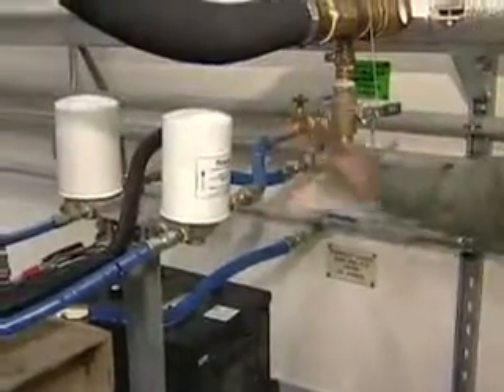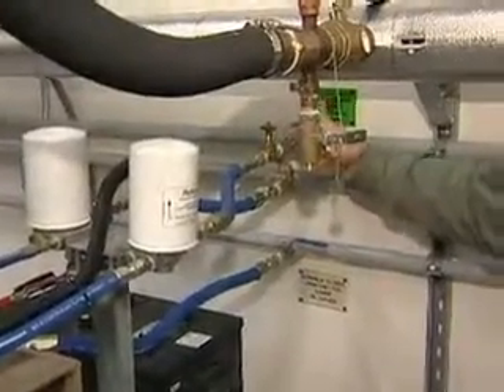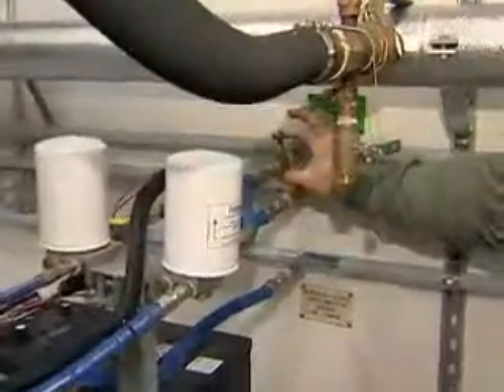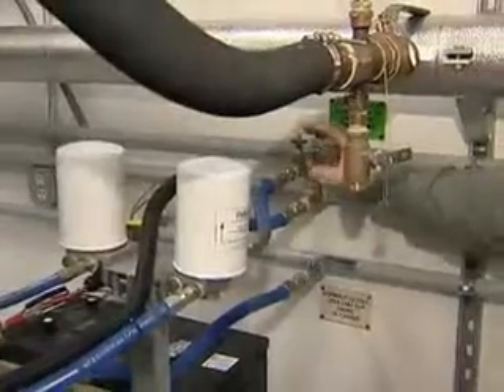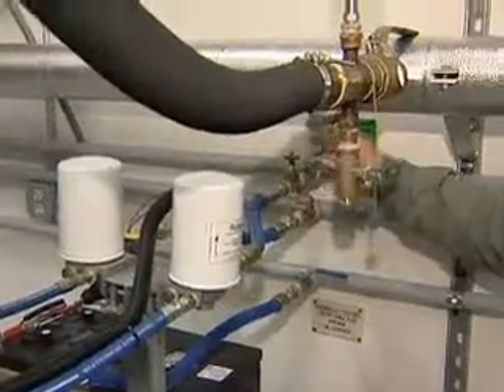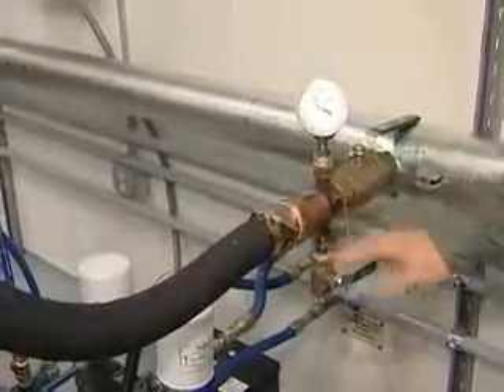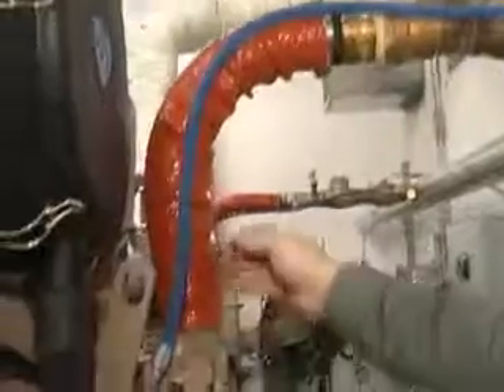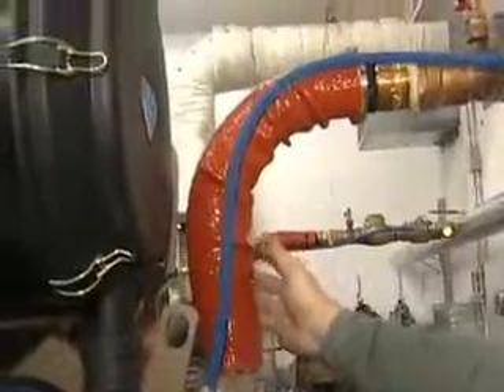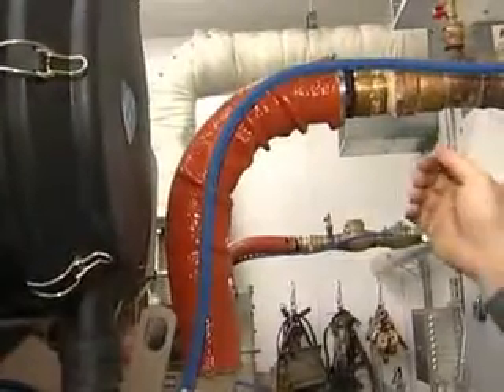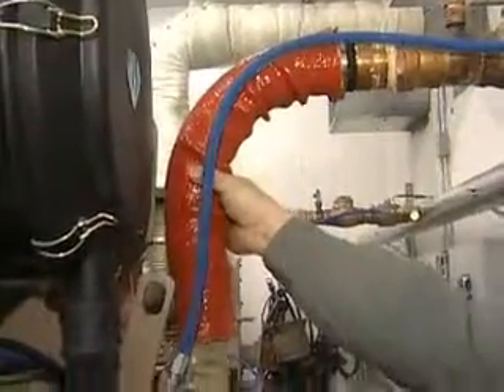We have our fuel valves. We have basically your standard shutoff valve for turning the fuel off. And then we have a Firomatic valve. This has a fusible link inside here that, in case of a fire, will melt that link and close that valve off. We've got our cooling system hoses that run back and forth to our engine. This is our return of the cold water back to the engine. On the high side here, we have our hot going out. If you notice, there's this orange blanket sitting on here. This is a protective blanket because we're so close to the exhaust system. The heat from the exhaust can dry out and crack this line, so we put this insulated blanket on there to protect it.